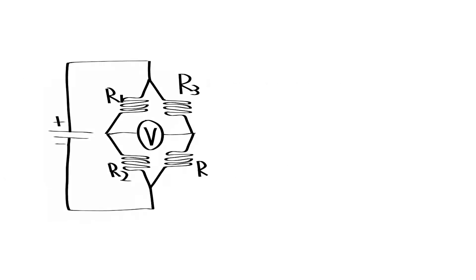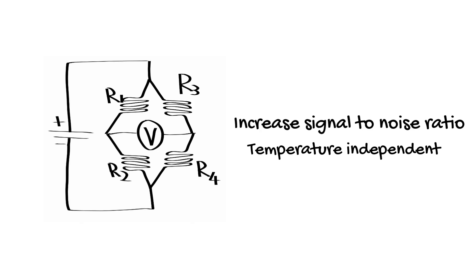Modern arterial line transducers no longer require a Wheatstone bridge to measure the resistance of the strain gauge. They have, however, retained the Wheatstone bridge. In this case, by having two strain gauges on either side of the Wheatstone bridge circuit. This increases the signal-to-noise ratio and also makes the system independent of temperature which can affect the electrical resistance of a strain gauge.